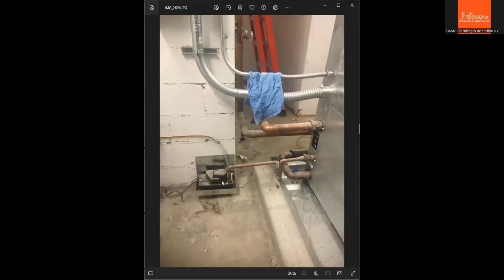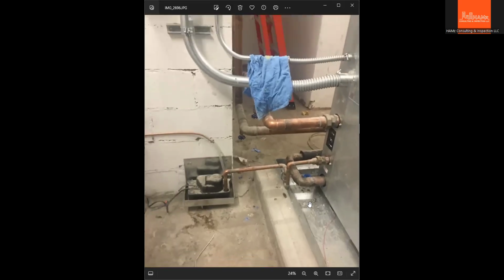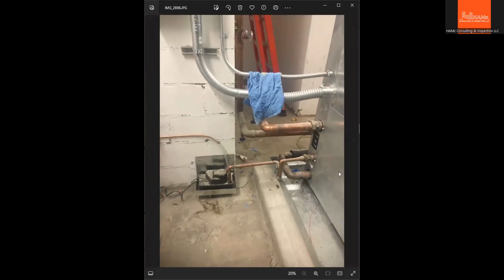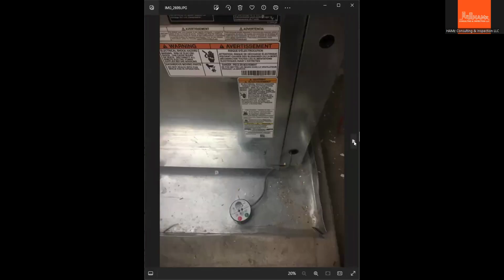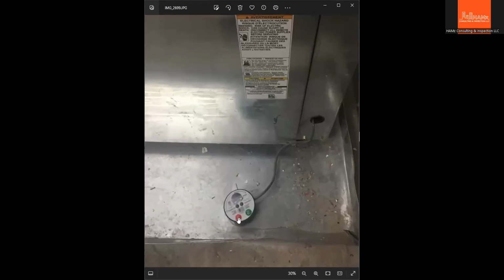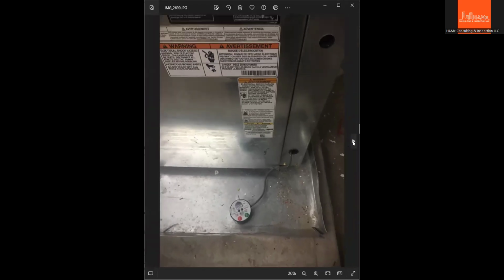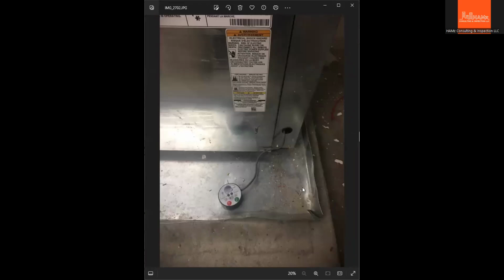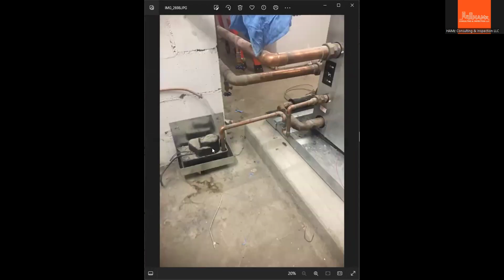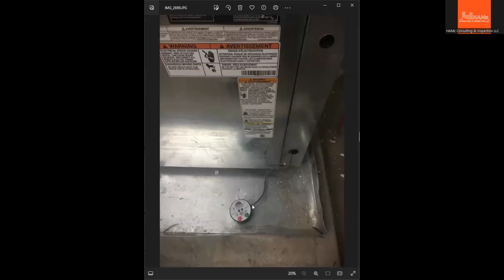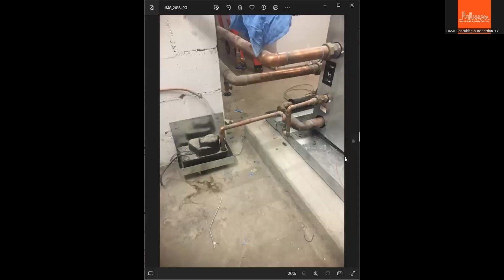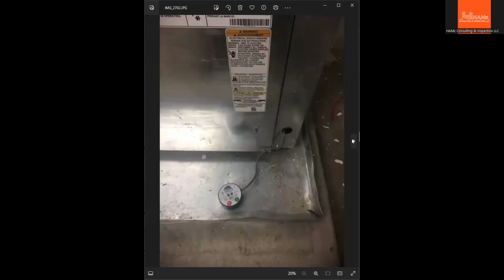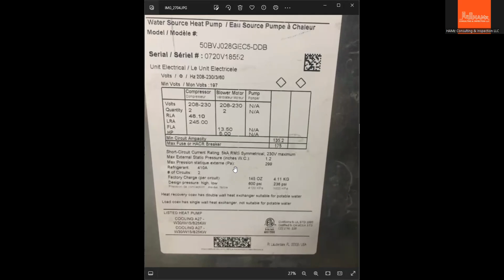So this is your pump, just in case you have flooded this auxiliary drain pan, the condensate pump, and you have the flood sensor. The purpose of this is, when you have a flood and it's going to spill out right here, it will stop the operation of the equipment to prevent flooding, or I think this will operate the condensate pump to throw out the excess water in the pan. And this is the nameplate.